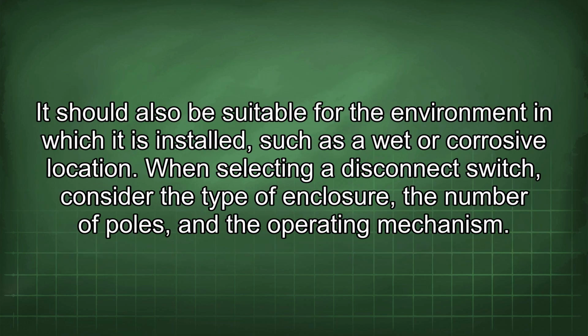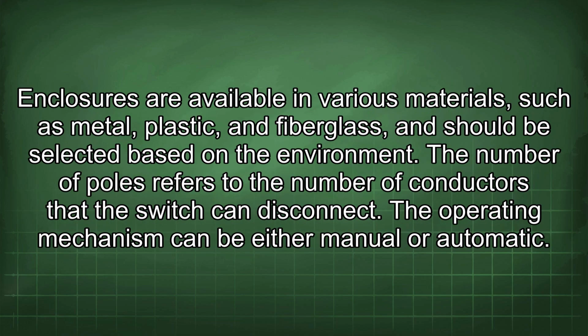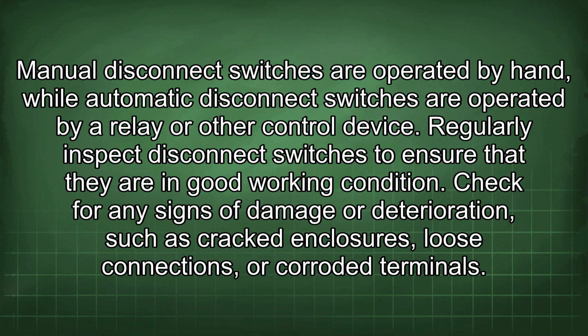It should also be suitable for the environment in which it is installed, such as a wet or corrosive location. When selecting a disconnect switch, consider the type of enclosure, the number of poles, and the operating mechanism. Enclosures are available in various materials such as metal, plastic, and fiberglass, and should be selected based on the environment. The number of poles refers to the number of conductors that the switch can disconnect. The operating mechanism can be either manual or automatic. Manual disconnect switches are operated by hand, while automatic disconnect switches are operated by a relay or other control device.